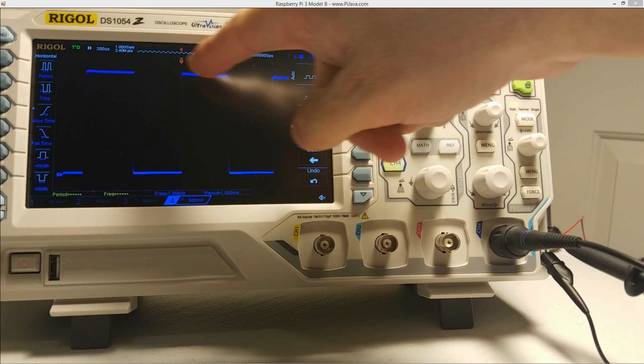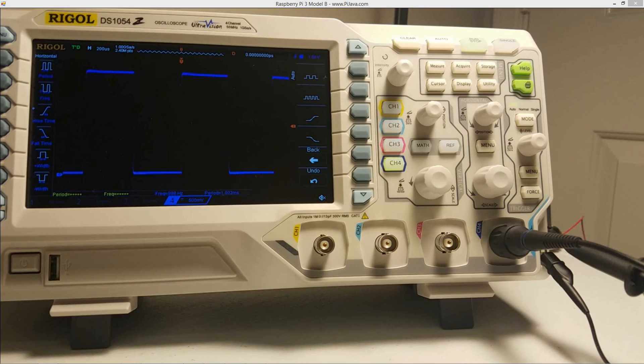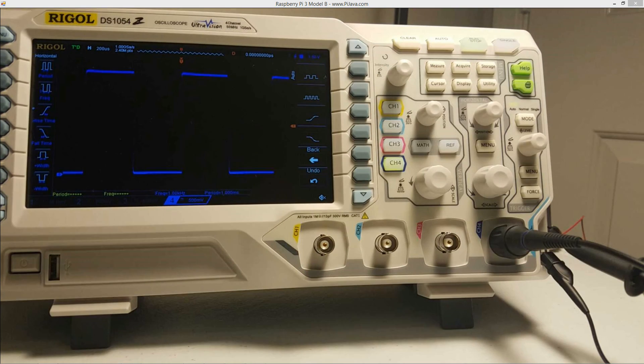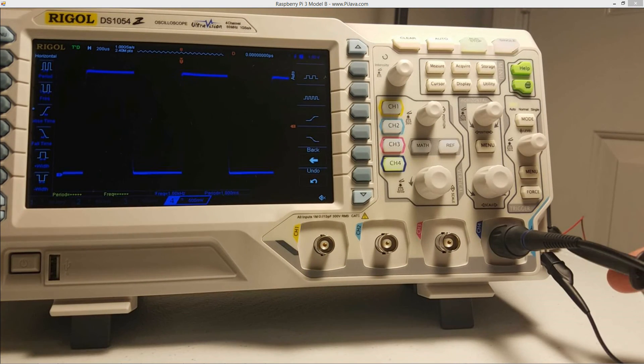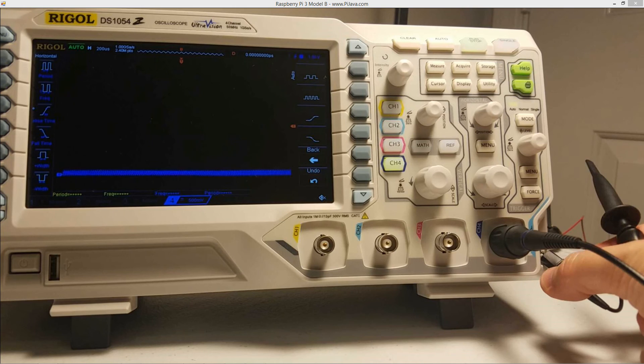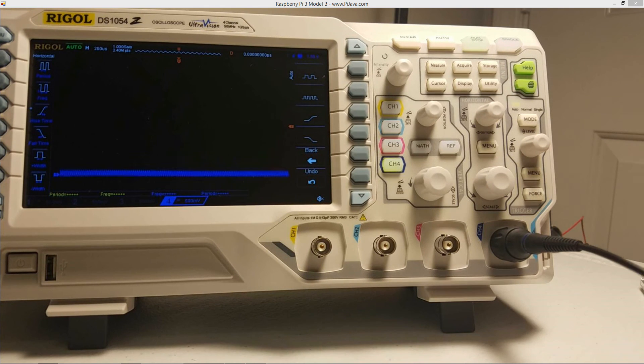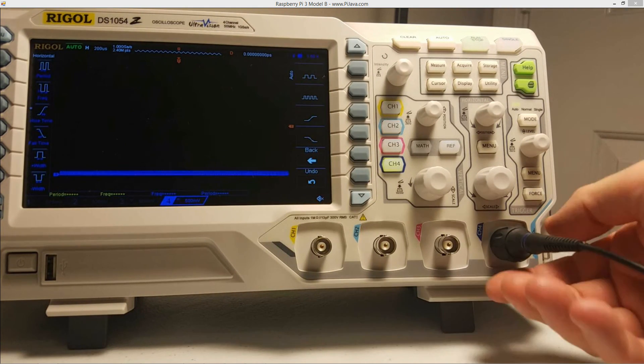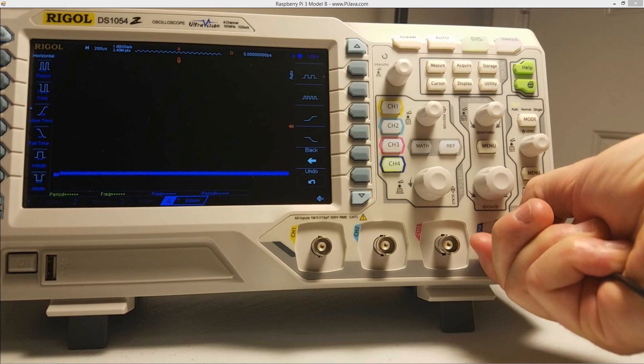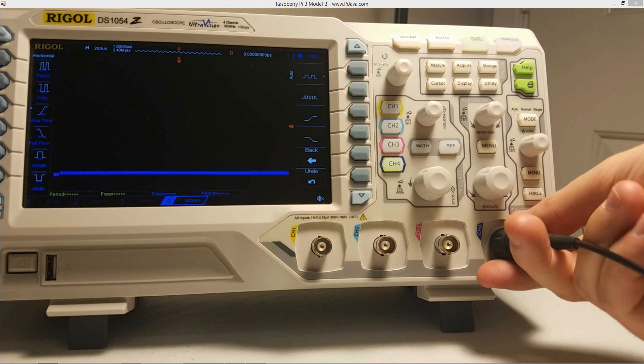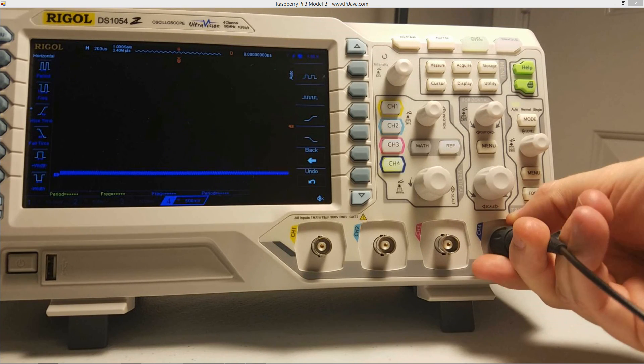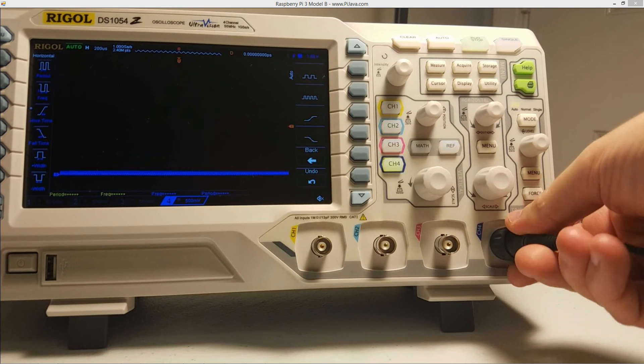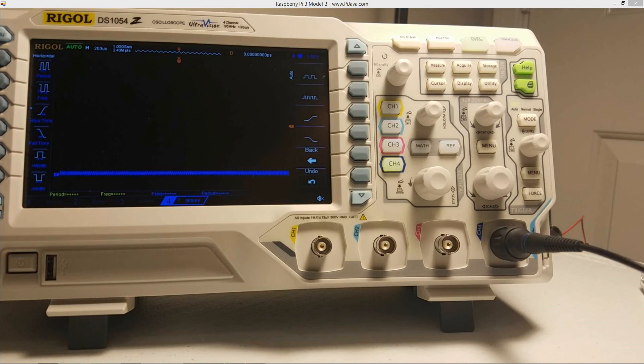So go ahead and come out here and right there. That looks pretty decent to me. We've got our flat, nice squared off waveforms here. I'm going to go ahead and unclip that, clip that. And we have now successfully compensated all of our oscilloscope channel probes there.